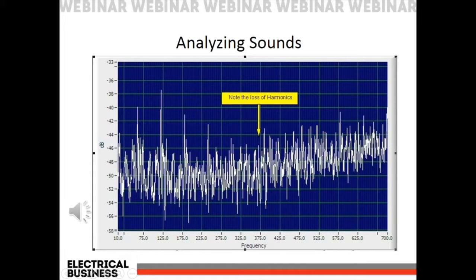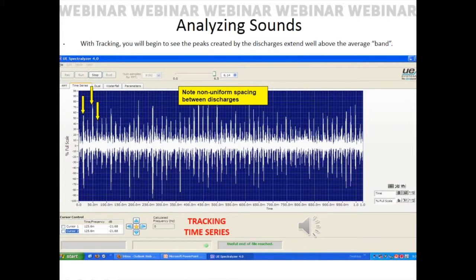However, there is still frequency content in between the harmonics that we see here, so that's a clear indication that this still is an electrical emission. And as we move from the frequency domain, which is the FFT, onto the time series, we can see the big difference between corona and what we're seeing here, which is tracking. Corona was a very evenly spaced harmonic with a lot more negatives on the end, where now we're seeing non-uniform spacing between discharges, as well as positive and negative peaks in the amplitude, to indicate that we've got a lot more flashover going on.